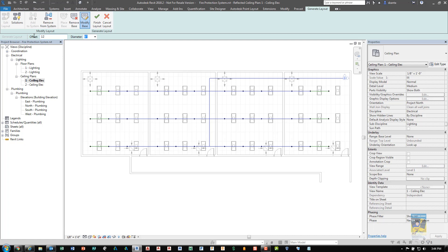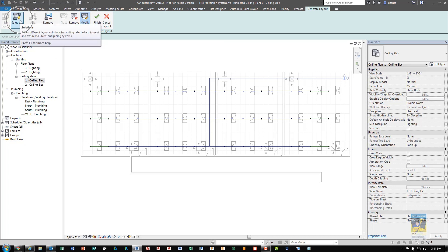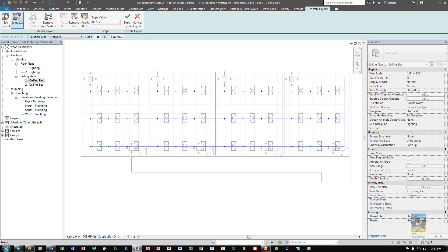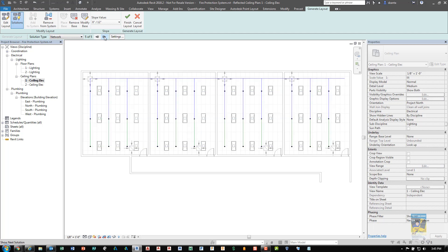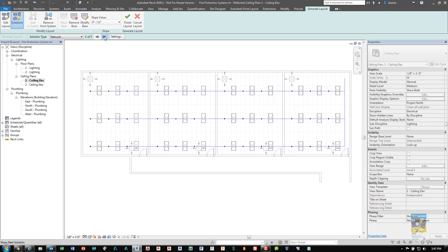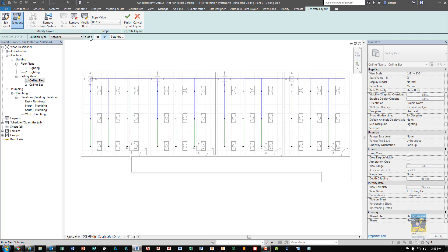So I'm going to specify it, say, 12.5 feet high. And the diameter, I'll specify, say, one and a half inch for now. Then click solutions to get back to your different solutions. And under network, you'll notice it changes. So earlier it had two possible solutions under network. Now it has five because I've placed that base point. Now you can use these arrows to cycle through the different designs and pick what you think makes the most sense for your design. This is all based upon, you know, your engineering design requirements and the architectural design requirements. So that way it doesn't interfere with any ductwork or piping.